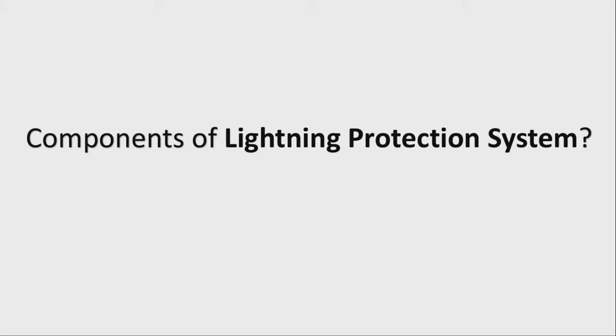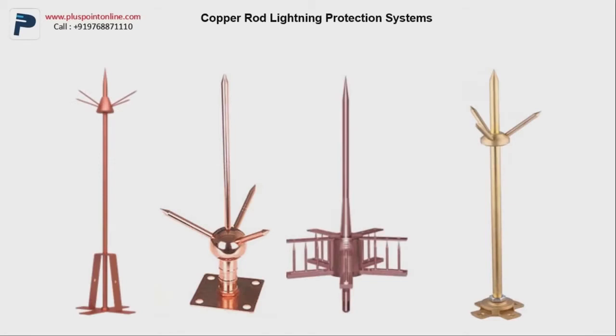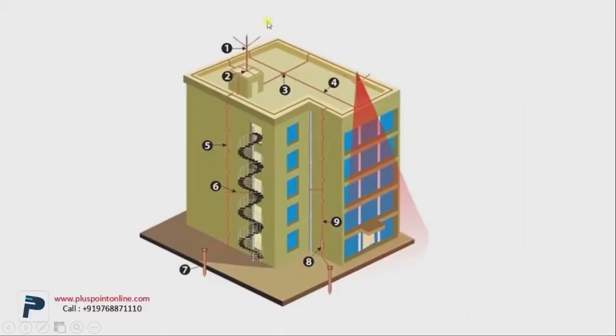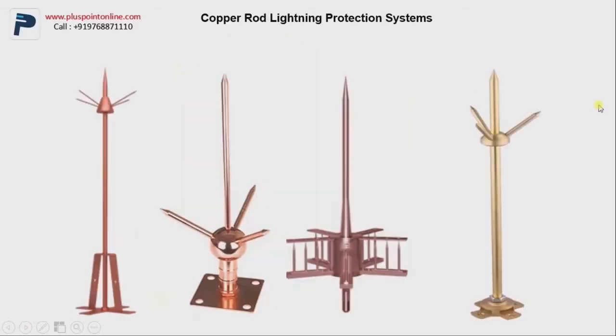Now let's get started with the components of the lightning protection system. The first one is the copper rod lightning protection system. In the copper rod, there are various components and each one has its own fundamentals. This is the rod made out of copper in which you can see the spikes attached. In buildings, these copper rods are installed in different areas and also the topmost part. These copper rods are combined with the copper plates, which are the copper strips that are attached to the ground. So if there's any lightning strike, the copper strip helps the lightning to go into the ground for the grounding. This system is known as the copper rod system, but this system has become quite outdated.